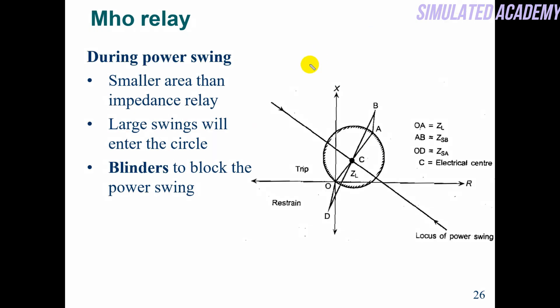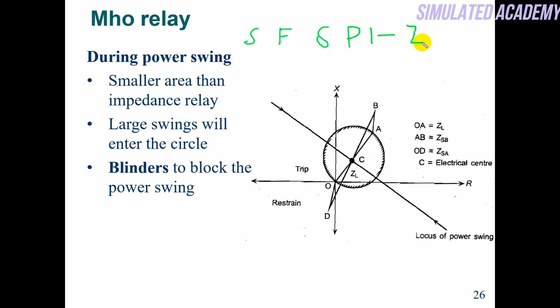Regarding power swings — we have discussed earlier what a power swing is. If switching or a fault occurs, the power will change, the current will change, the Z value will change, and a point moves from zero toward the center of the impedance diagram.